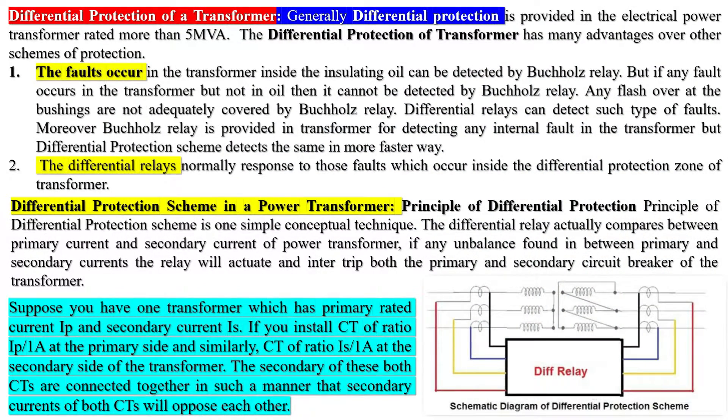The concept of in-zone faults and out-of-zone faults is employed to differentiate between fault types. Specifically, out-of-zone faults — also known as through faults — require the differential protection scheme to remain stable, meaning it should not operate during through fault conditions.